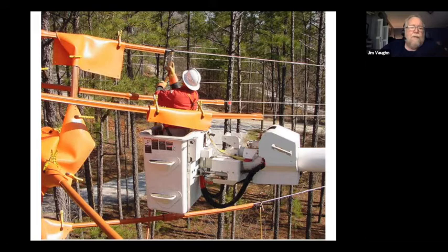Yeah, okay. There's nothing wrong with doing that in order to accomplish a cover up. But the problem with tape is it leaves a sticky surface that can be contaminated and it makes it hard to clean. So most utilities have a rule, don't use tape. They prefer that you use clamps in order to get it in there, or buttons with magnets on them or something like that. If you do use tape, when you take that blanket off, that blanket ought to go in for cleaning using the blanket cleaners that are available from manufacturers, because that tape will gather contaminants on it and can make the surface of the blanket conductive, and we don't want to do that. So thanks for that question.